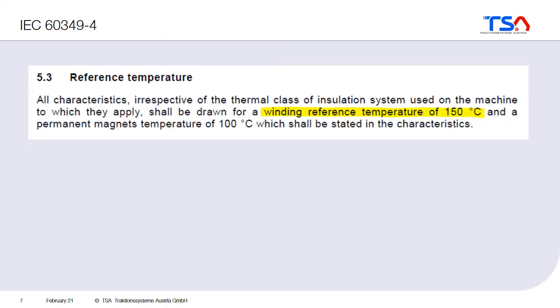Chapter 5.3 already gives us a hint about the typical temperatures for traction machines. Traction machines in the rail business are usually highly utilized, so temperatures are higher than in typical industrial applications. If you put data into a datasheet, you should use special reference temperatures — for example, for the winding you should use a reference temperature of 150 degrees Celsius, and for the permanent magnets, 100 degrees Celsius.